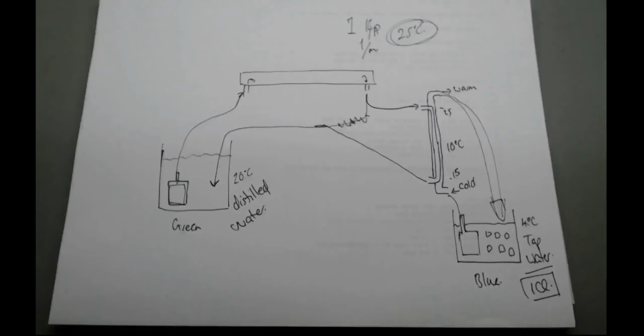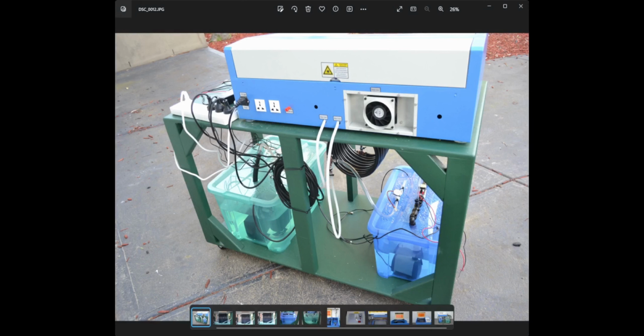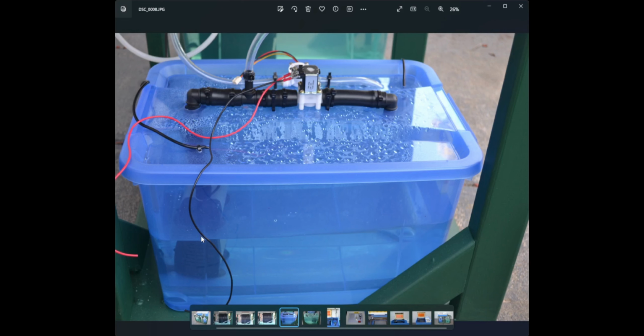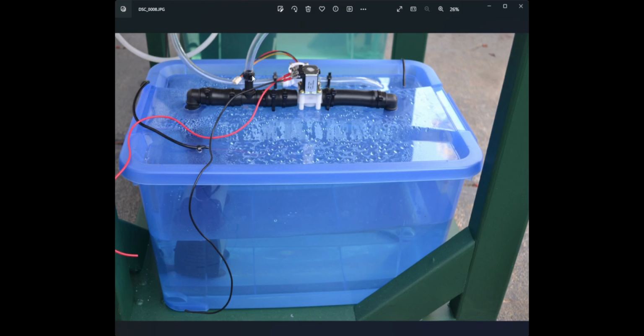So if I flick back to the photo, that button there, and I'll switch to a close-up of the blue tank. Right, pumps here. So that's pushing water up here, and then the water travels up here into the water chiller. Now, if I want to turn the system off, I don't want to turn this pump off, because pumps don't like being turned on, turned off, turned on, turned off. So what I've done is I put a bypass solenoid here. When I activate the solenoid, the water will follow the easy path and just cycle around the side of this tank.